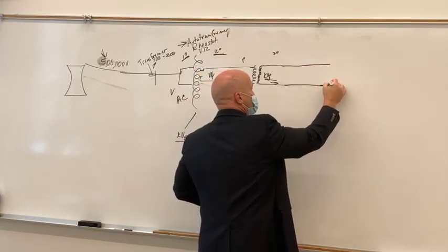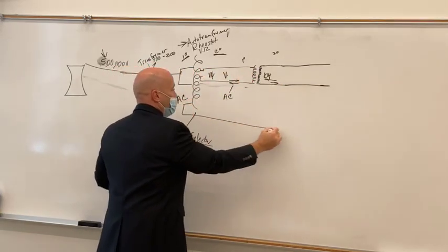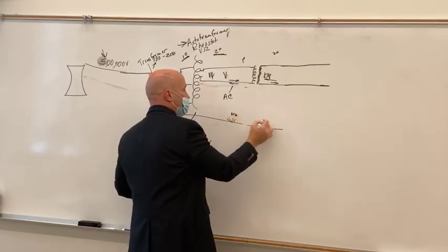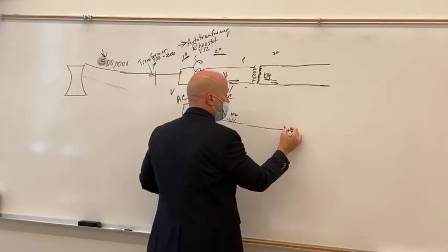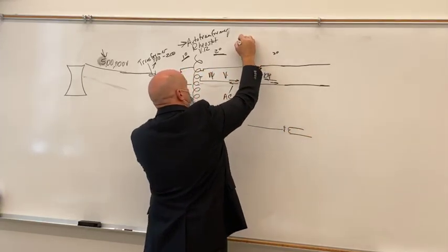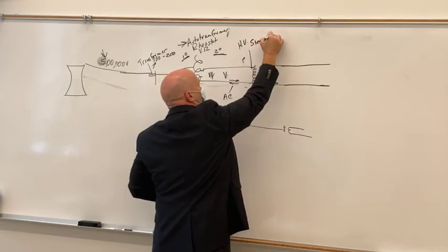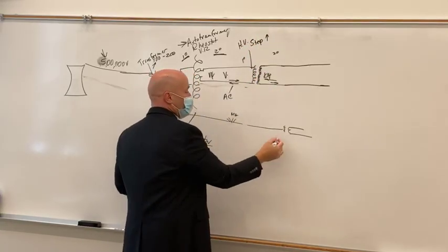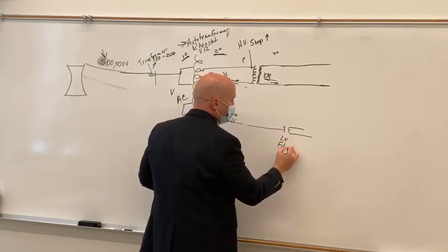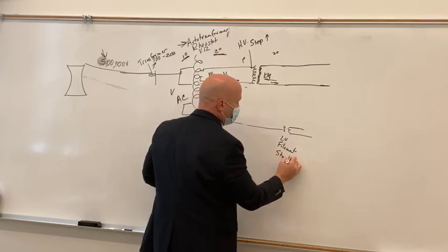To another transformer. We're done with this portion of the transformer. You're thinking about down here going into the mA selector, and then you've got the reverse of that, where we've got a step down transformer. We call this our high voltage transformer, which is also a step up transformer, right? So we step up the voltage. This one, on the other hand, is a low voltage transformer. It's a filament transformer, and it is a step down transformer, right?